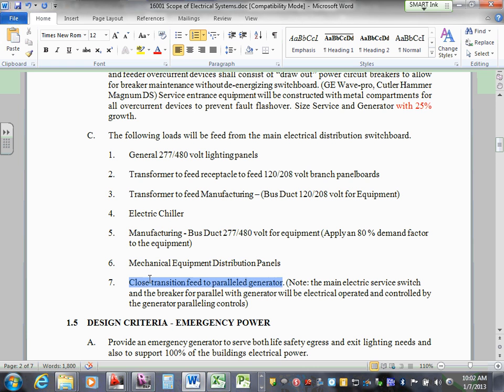Close transition feed parallel to the genset. The main electric service switch and the breaker for parallel with the genset would be electrically operated, controlled by the generator parallel controls.